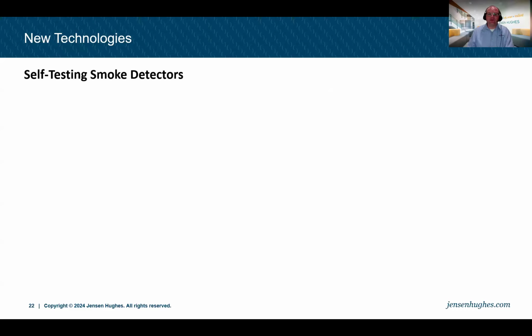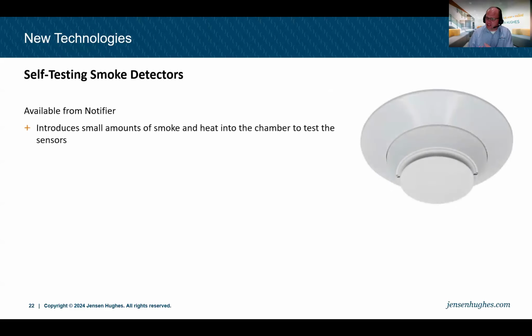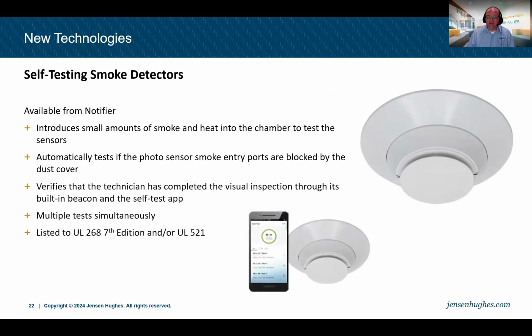And self-testing smoke detectors. Have you ever got tired of going to each smoke detector with maybe a smoke pole or a smoke can? You ever want that smoke detector to test itself? Well, this is available from Notifier fire alarm systems. Each device introduces a small amount of smoke and also heat into the chamber to test the sensor's capability. It automatically tests if the smoke entry ports are blocked by, let's say, a dust cover on it. So that's convenient. And it verifies that the technician has completed the visual aspect through kind of a built-in beacon and a self-testing app that a technician can carry around on their phone.